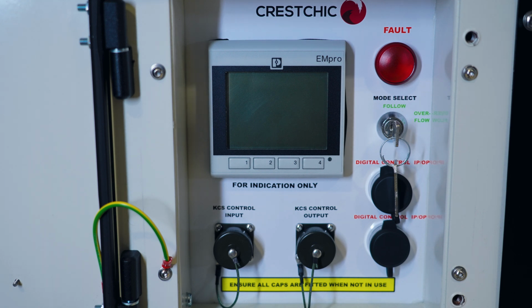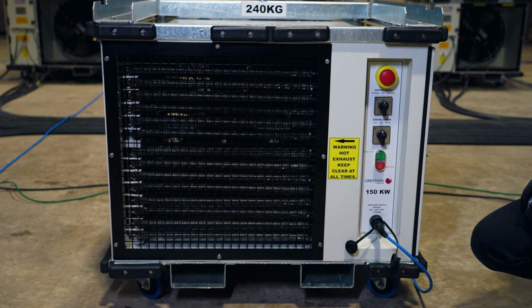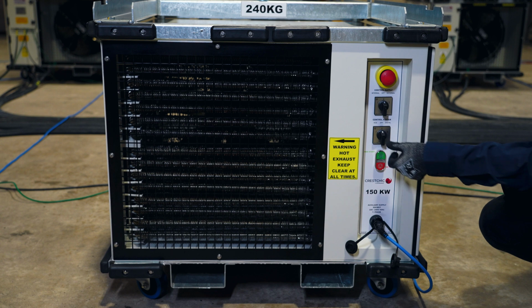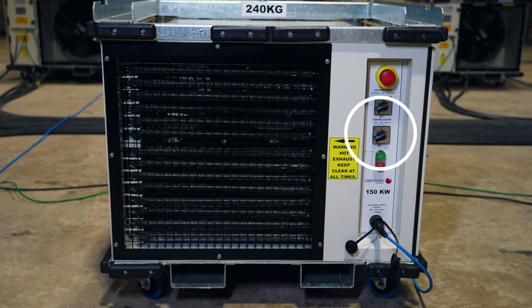This works the same with the digital controller. As per the previous demonstration, we have a 3-phase 415 volt supply to the load banks. We are using an auxiliary supply for the load bank's control system, therefore we can switch the control switch to external. We check the emergency stop is out, select the loading mode, in this case we will use follow, and select the controller type, which is the digital controller. This should be completed on all the load banks.